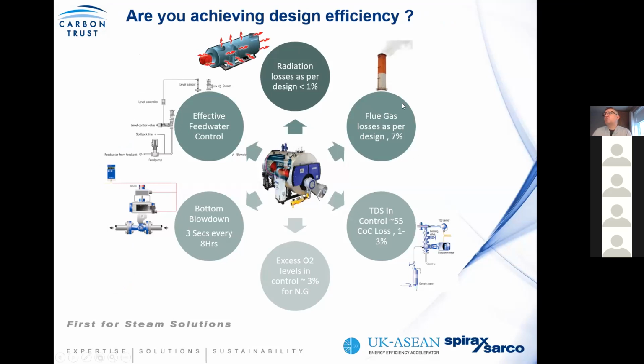So again, we mentioned the flue gas losses, the TDS control, and excess oxygen, which was discussed in the introduction. The ability to recover this kind of energy and operate at a certain level of excess oxygen will be determined by your fuel source. Where you have natural gas, for example, there is greater ability to recover more energy because it's clean burning. You can get more of the energy that's entrained in the flue gases because you're not concerned about particulates or fly ash, for example, when burning biomass. So there are different constraints.